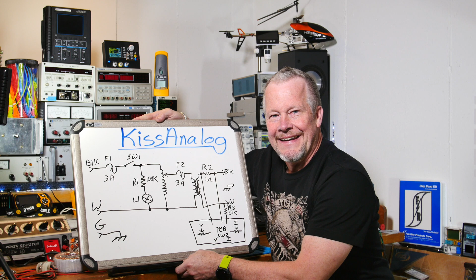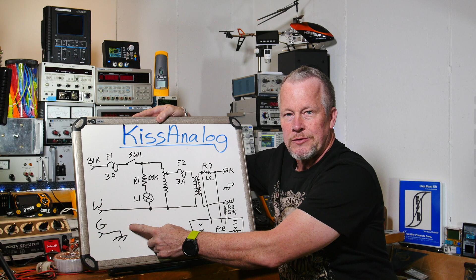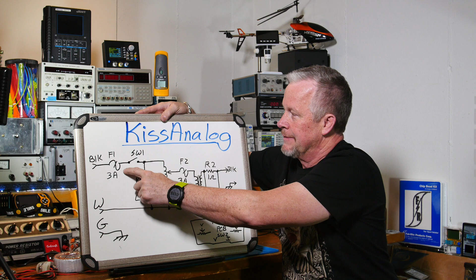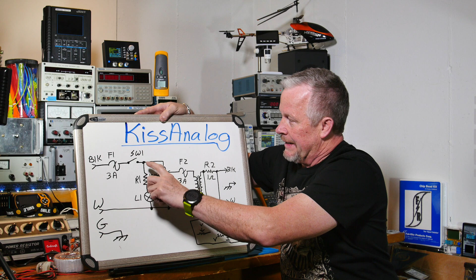We have 3 wires coming in: black, white, and green, coming in the power cord. The green comes immediately into the chassis where it should, and that has to make a good connection in case something shorts to the chassis, so it goes back and pulls the circuit breaker. We're going to check that out. The black wire comes into a fuse on the exterior of the panel, then goes through a switch, and on the other side of the switch we have 100K that lights up this lamp.